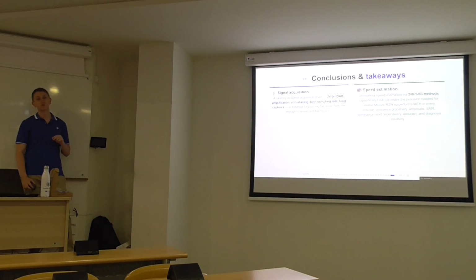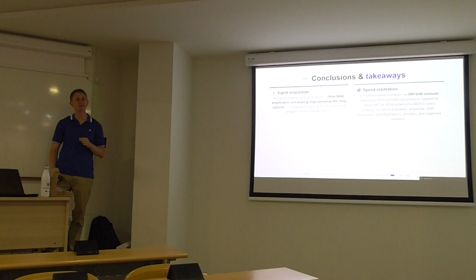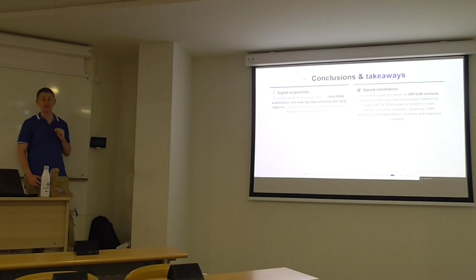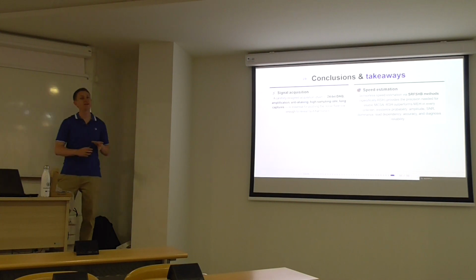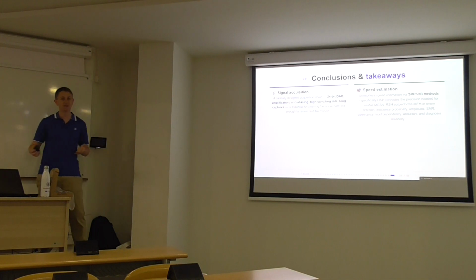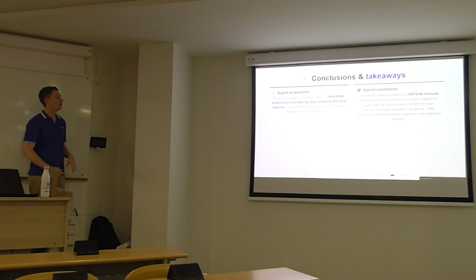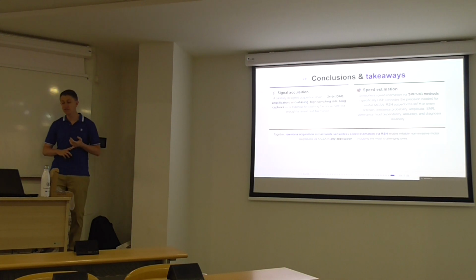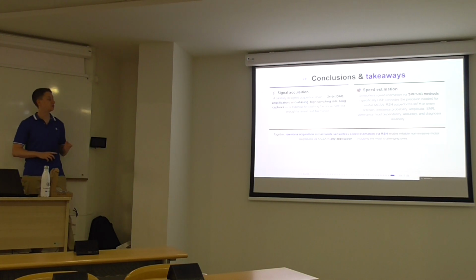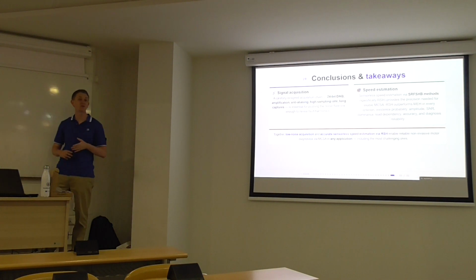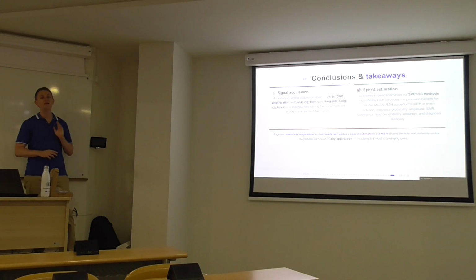estimating the speed through the rotor slot harmonic is the best option you have. Because they outperform the mixed eccentricity harmonic in every criterion we have studied, and because they are the most compatible with MCSA. It's just the same process. We measure one current, we analyze the spectrum. So, together, low noise acquisition and accurate sensorless speed estimation through rotor slot harmonics enable reliable, non-invasive motor diagnostics via MCSA in any application.